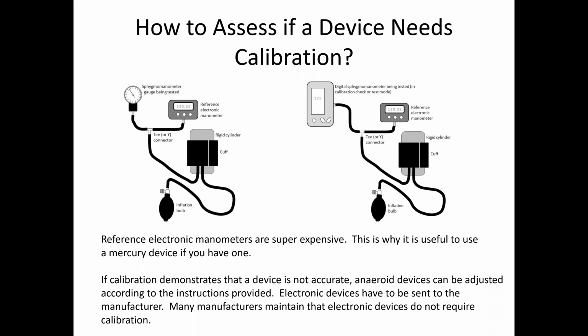I will also say, though, that we don't think electric or automated devices require a lot of calibration, and that's simply because of the way they work. The only thing that would probably go in terms of componentry is the pressure transducer and the cuffs, of course, but the cuffs you can see when they're worn out and need to be replaced. And the pressure transducer, from testing that I'm told by many different companies, doesn't really drift over time unless that unit has been damaged in some way or dropped. And so probably the automated, oscillometric devices don't require a lot of calibration, but it's still important to be able to test them to make sure. Next slide, please.